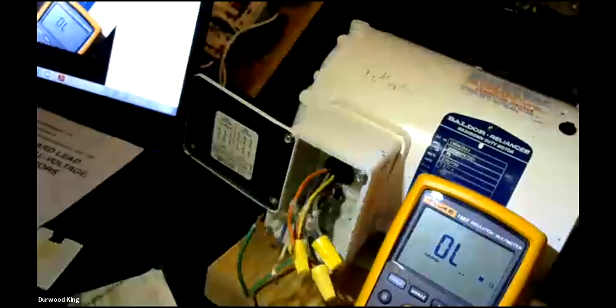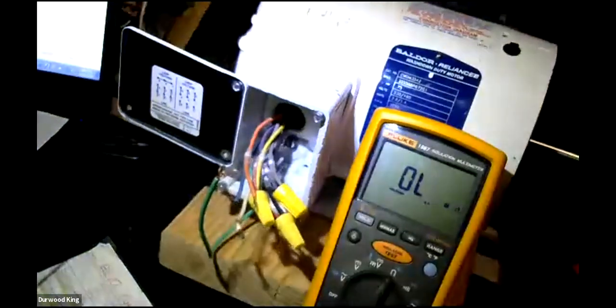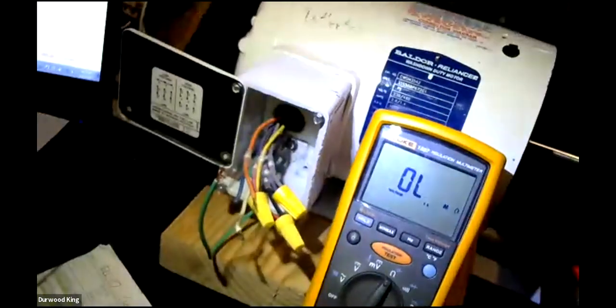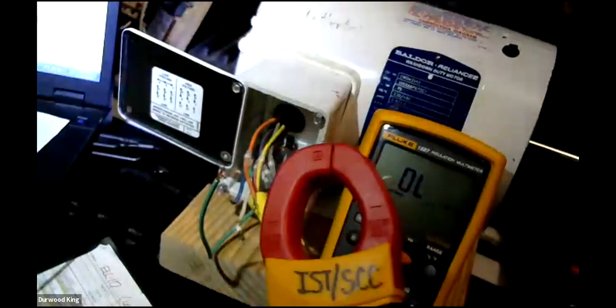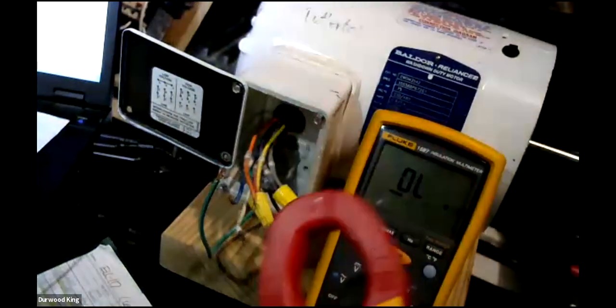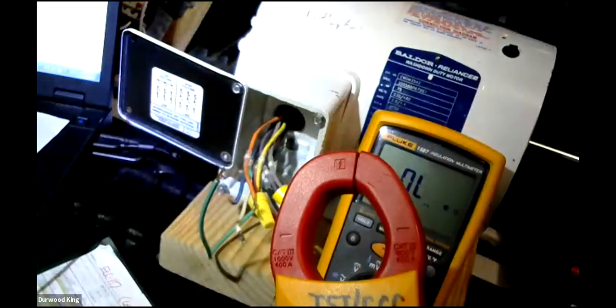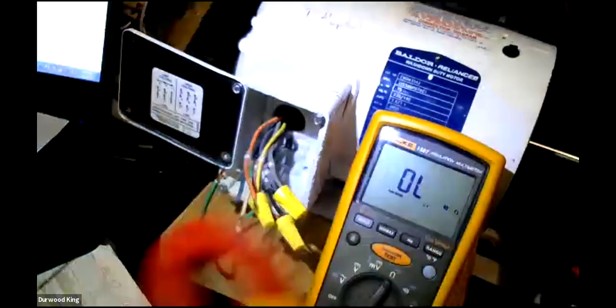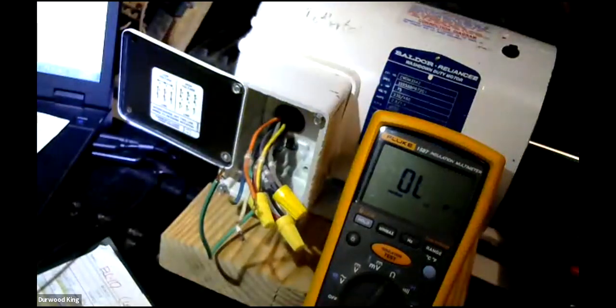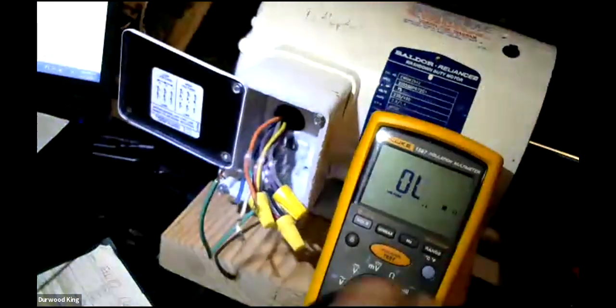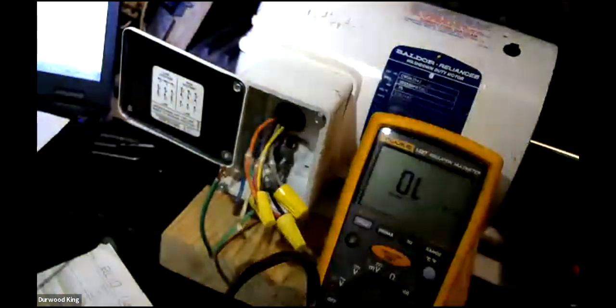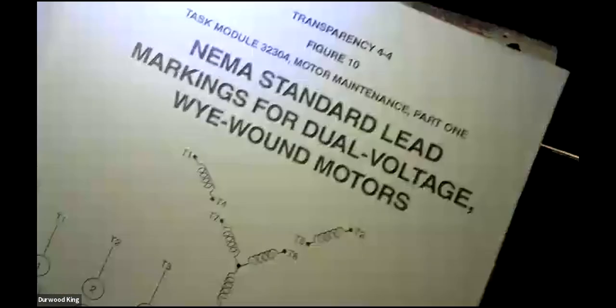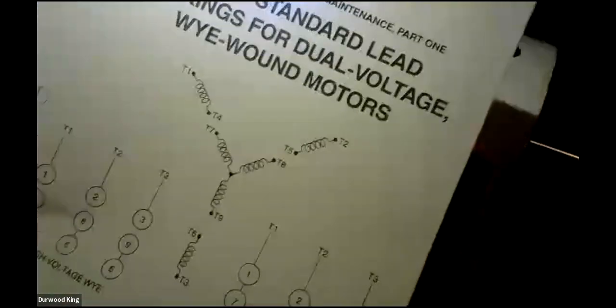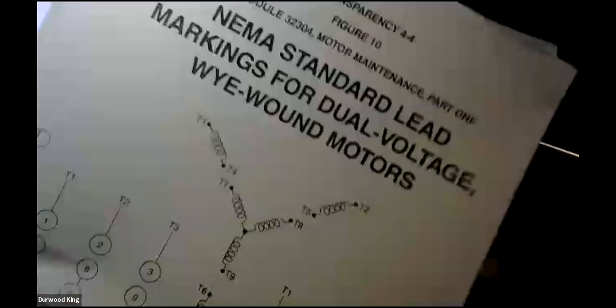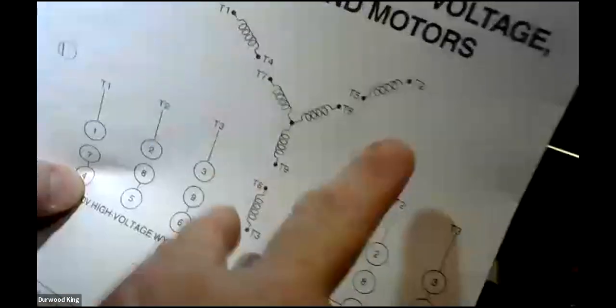Here's what you do. You want to keep a log every couple of weeks. You want to do an amp check per leg, a PM, and record that on larger motors that are critical. Do that every so often. And if you see a change in amps, you could also do a meg test on larger motors every so often, and a resistance test like we're looking at doing right here. When you do a resistance test through the windings, and you check through them, let's say that this month you get a resistance reading of 20 ohms in every direction here, 20 and 20 and 20.